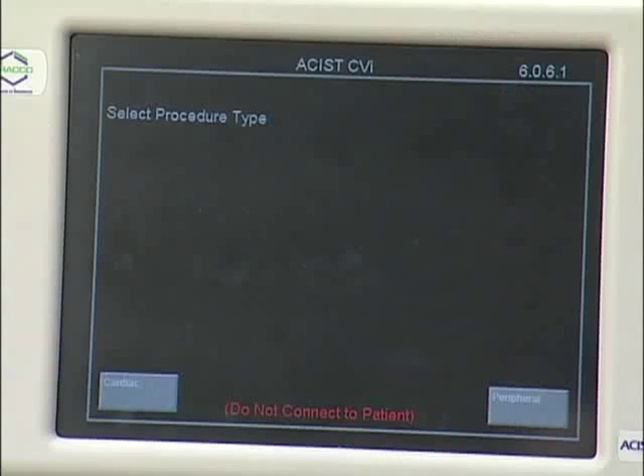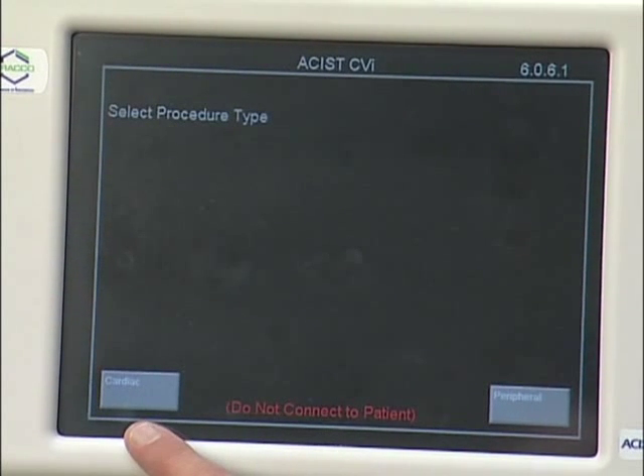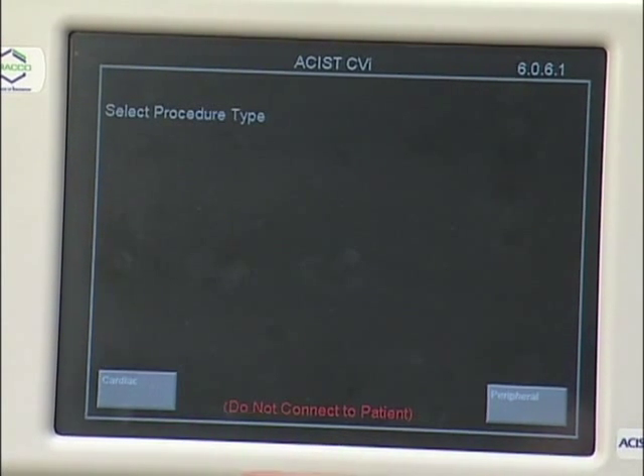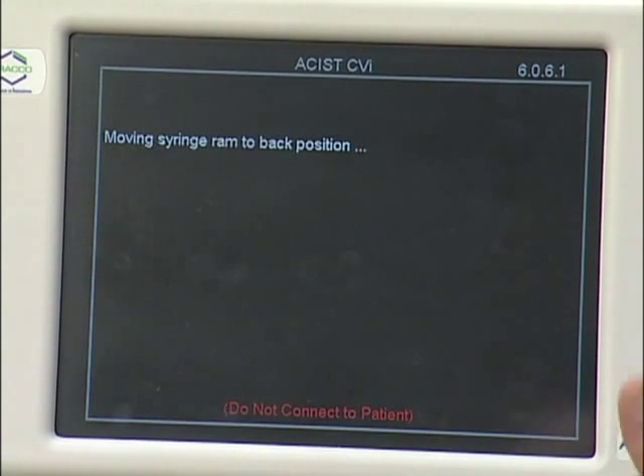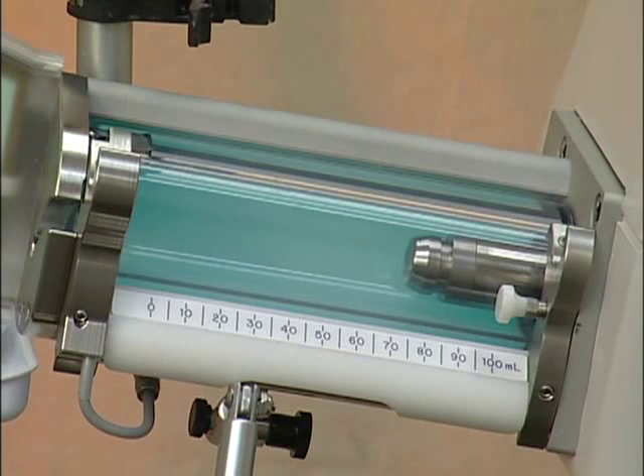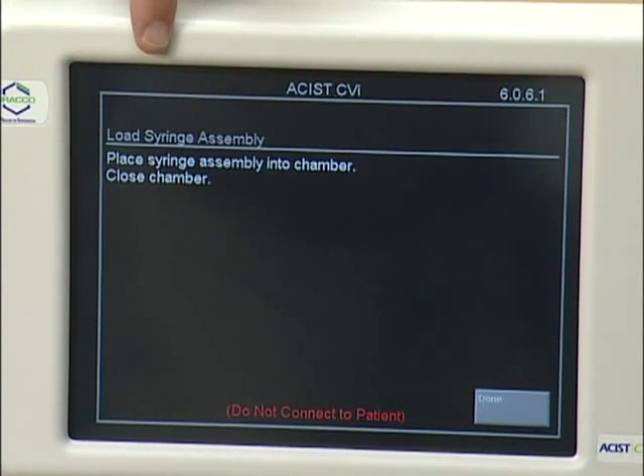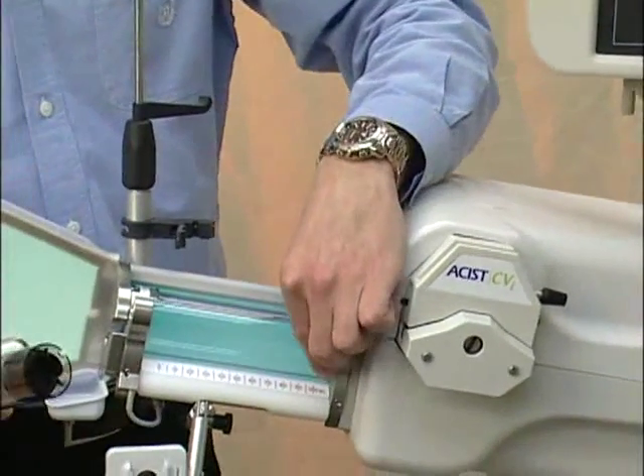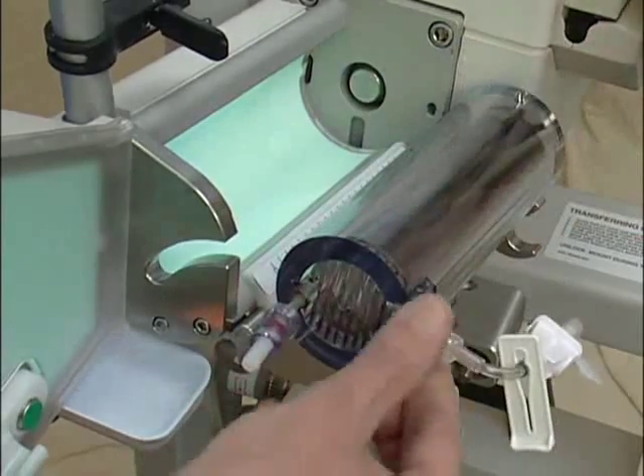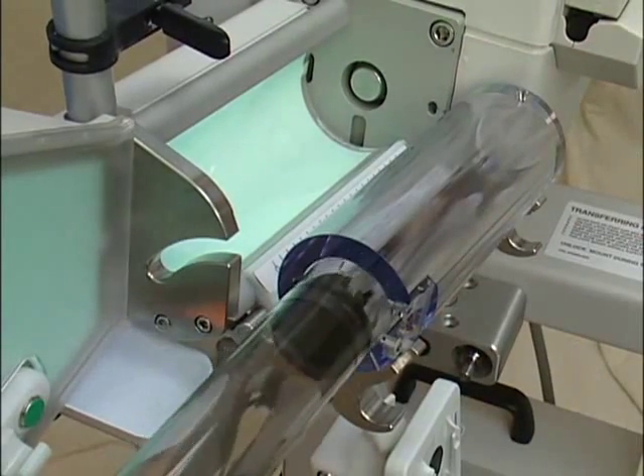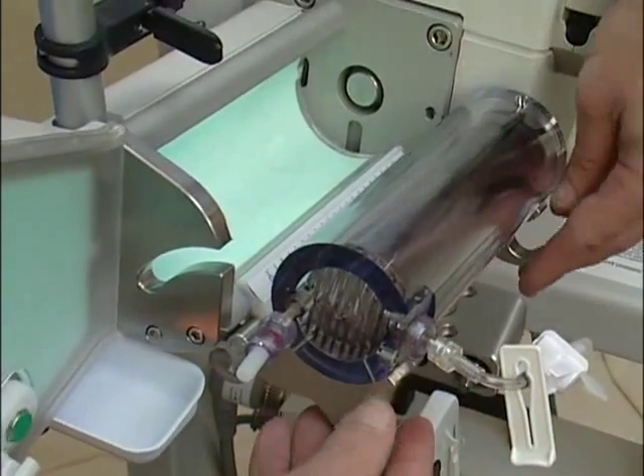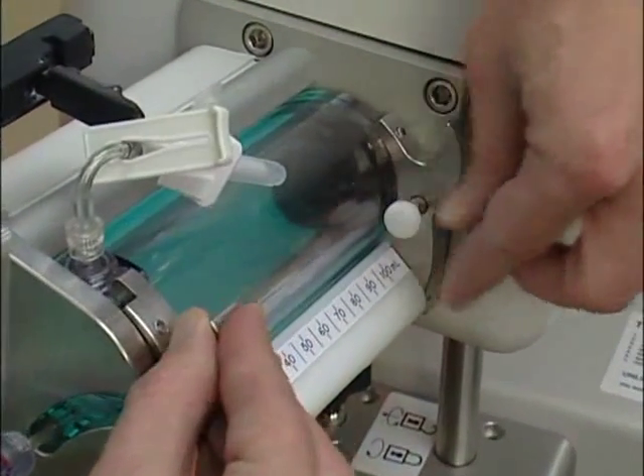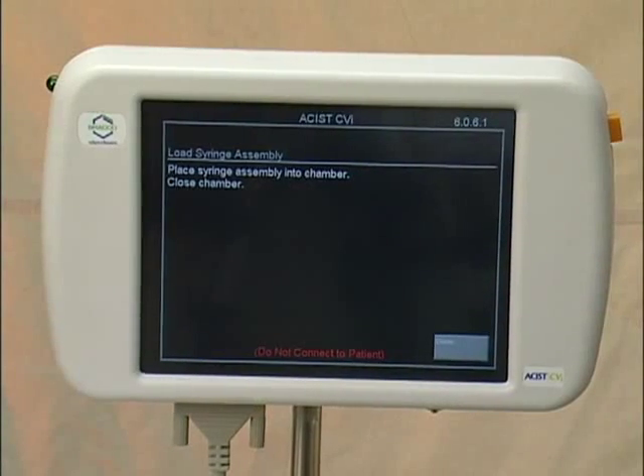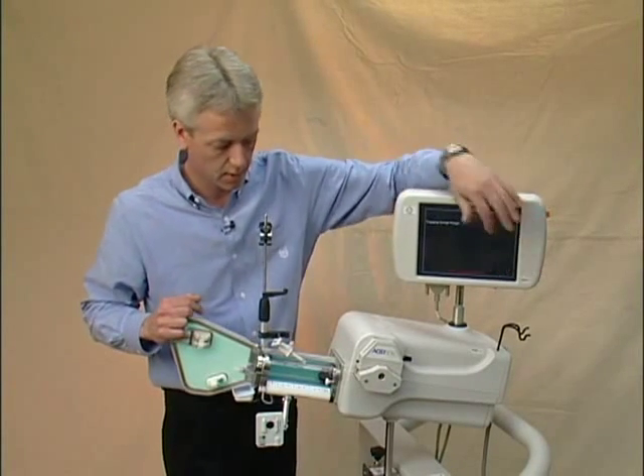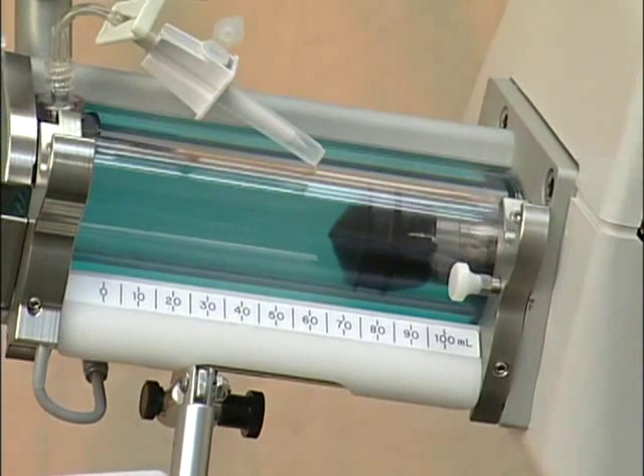First, we'll press the start button. Pressing the start button gives you the choice of the cardiac mode or the peripheral mode. For this demonstration, I'll choose the cardiac, in which case that initiates the calibration of the RAM. The system then comes to the load syringe screen, where it will prompt you to load our A2000 syringe. This is done by releasing the white pin on our sleeve, which allows you to rotate the sleeve outward and insert the syringe. Once that is done, rotate back inward and make sure the locking pin is in the locked position. Once we've inserted the syringe, we can press done on the screen, and you'll see the RAM come forward and engage the wiper.